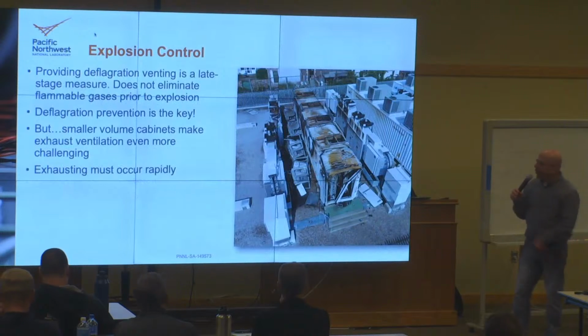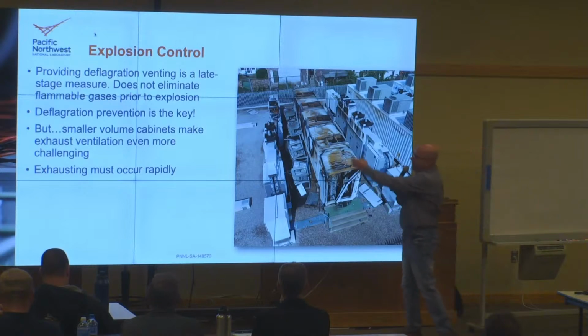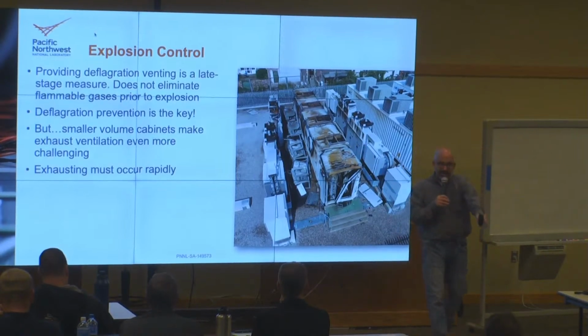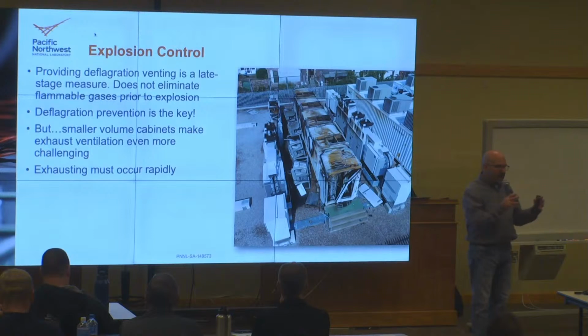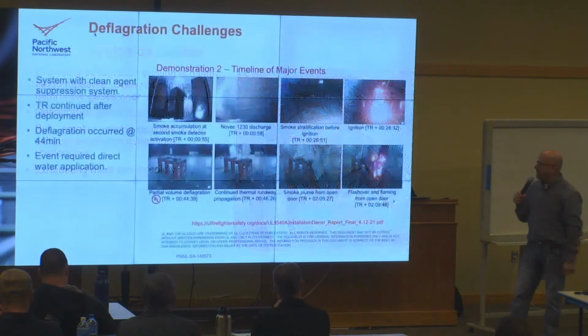This system here showed what can happen when you don't have it. And in a system like this, where you have a lot of free air volume, because there's that whole walkway down the middle, think now if you have a cabinet where there's just inches between the walls and the batteries, a lot less free air volume. How quickly would those fans need to operate, even quicker? So it's going to be even more challenging to have an exhaust system in a cabinet.